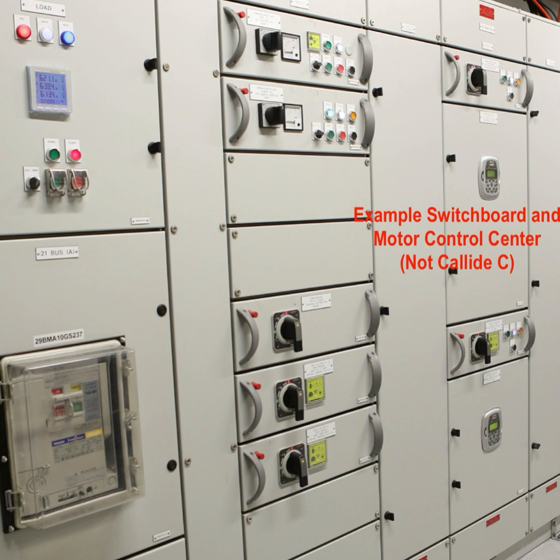Right, so now let's circle back to why the DC bus voltage decay took 2 seconds. As mentioned earlier, the DC bus voltage didn't just instantaneously drop to zero. There's no such thing as instant anything. Magnetic fields take time to collapse, and bleeding out inductance and capacitance is a well-understood electrical reality. What many people don't appreciate is that scale influences this time delay.